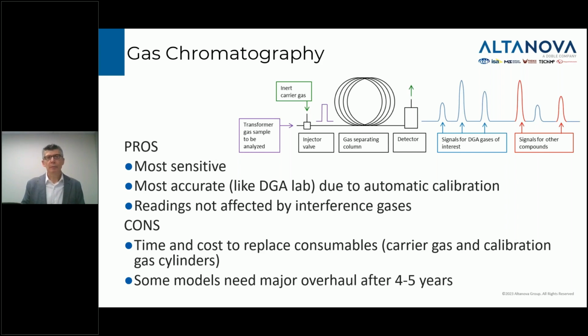And one of the nice things about the gas chromatography technique is those interfering compounds, they actually don't interfere. They come out of the chromatography column at different points in time. That's what I'm trying to indicate with these red peaks here. Those are the signals from these interfering compounds, and they're in a different location compared to the DGA gases. So they don't introduce a measurement error for a measurement of the target gases. So that's great. It's a fabulous measurement technique.